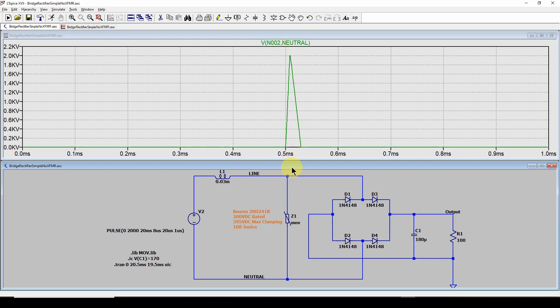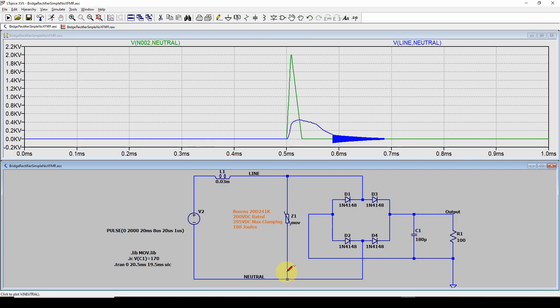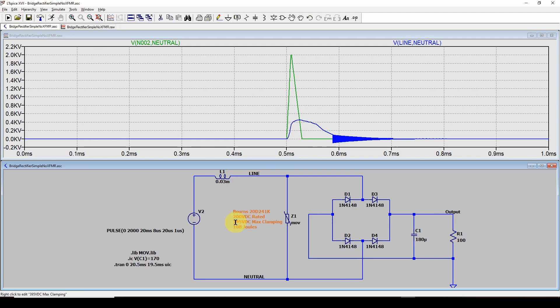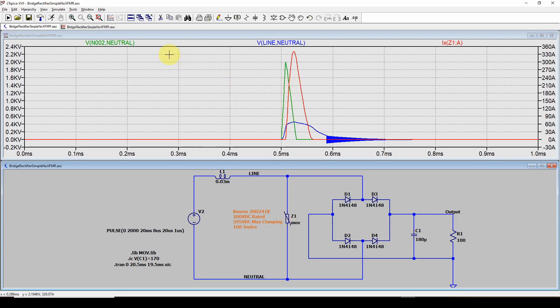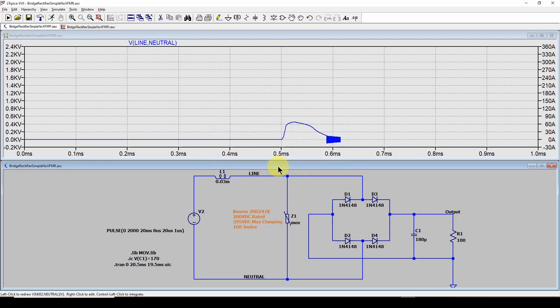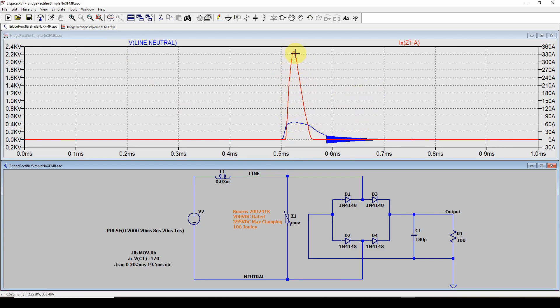Now, what does that look like across the MOV? So we do the same thing. We get a differential across the MOV and you're down now to 0.4 KV or 400 volts. And remember, this thing is rated for maximum clamping of about 400 volts. So that makes sense. And you've limited the voltage across this MOV to about 400 volts. So it's doing its job, but we said there's going to be a lot of current involved. So now let's measure the current through this MOV. So we'll click on that and let's get rid of this initial pulse. And here is the voltage and this red is the current. You can see it's up 330 amps for maybe 30 microseconds.